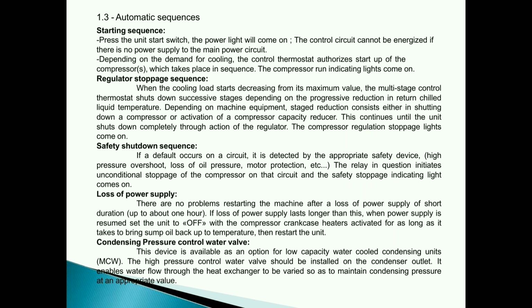1.3 Automatic sequences. Starting sequence. Press the unit start switch, the power light will come on. The control circuit cannot be energized if there is no power supply to the main power circuit. Depending on the demand for cooling, the control thermostat authorizes startup of the compressors, which takes place in sequence. The compressor run indicating lights come on.